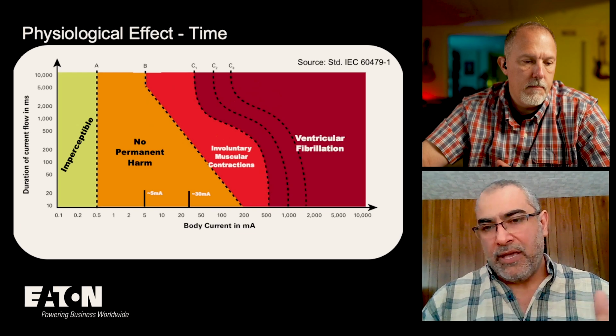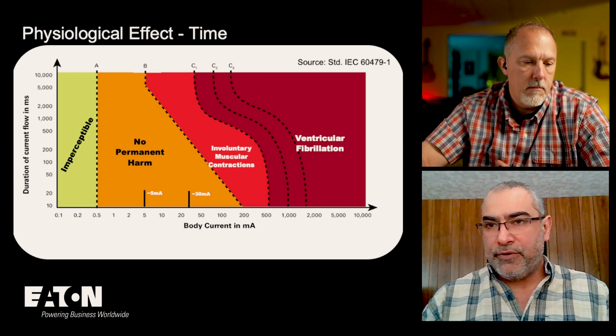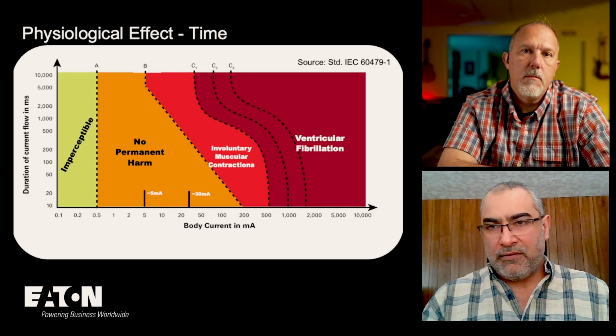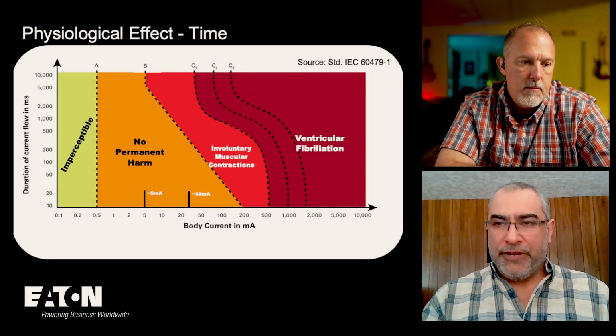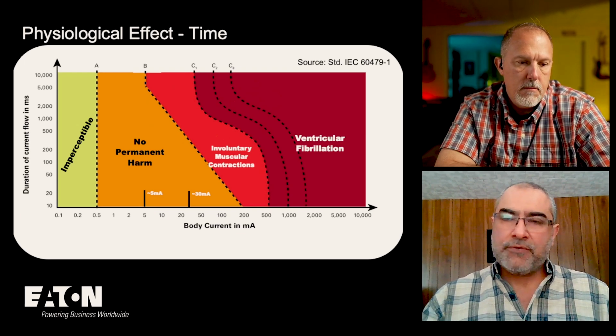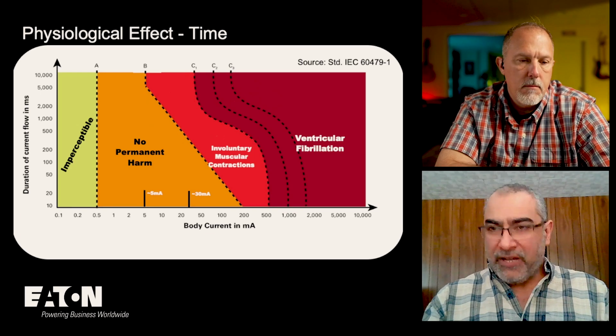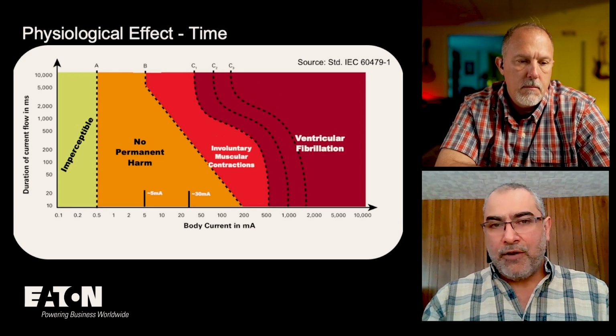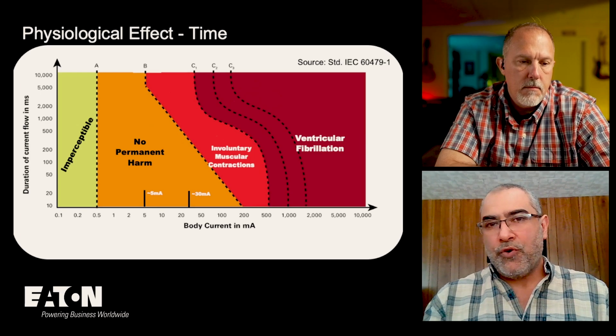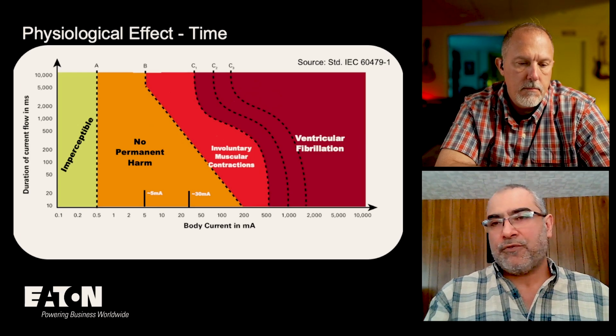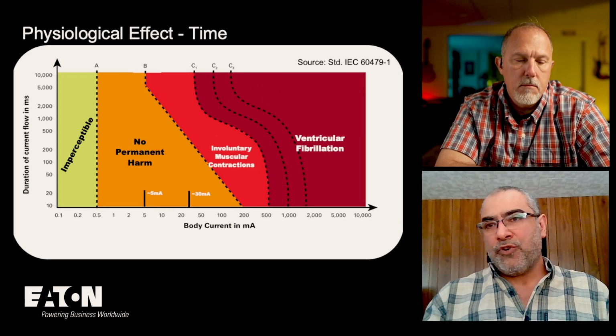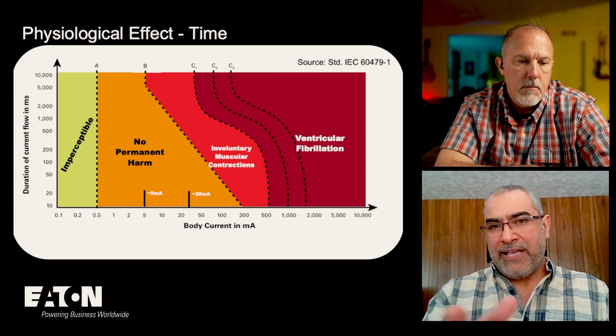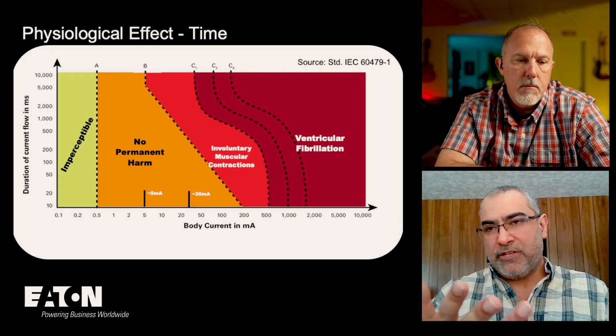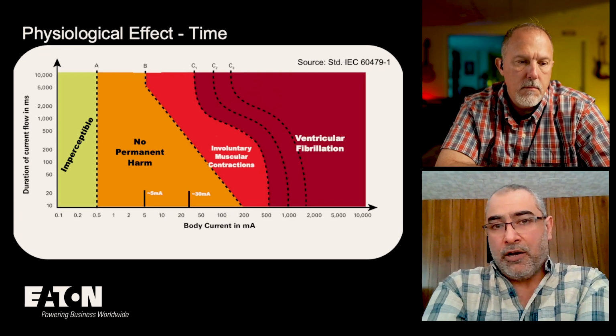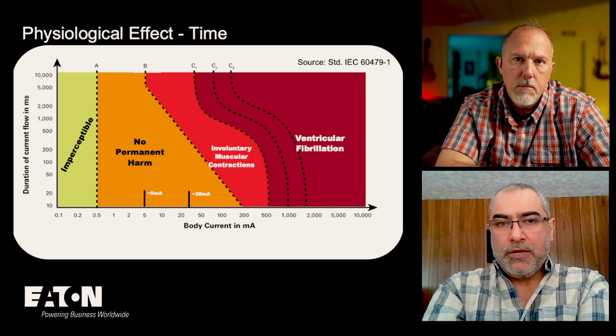In Europe, they have a different philosophy, so they use 20 or 30 milliamp, which technically means you may have some let-go issues and not be able to let go, but the idea is you're going to trip quick enough without getting into the light red zone. So it doesn't provide let-go protection, but it sure enough provides ventricular fibrillation protection - you don't get into the dark red zone where it's almost guaranteed the heart goes into fibrillation.